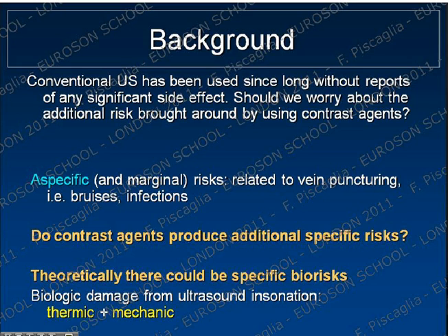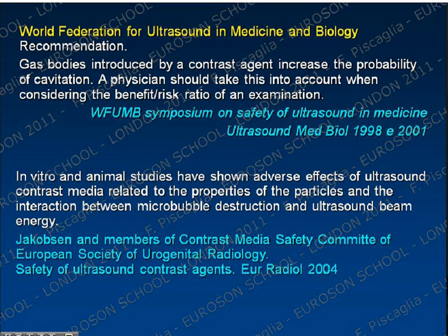Theoretically, there could be some specific bio-risks. Biological damage might be brought by the insonation of ultrasound with gaseous particles and might be produced as thermic or mechanical risks. And this is due to the interaction of ultrasound waves and gas bodies, because this interaction increases the probability of cavitation.